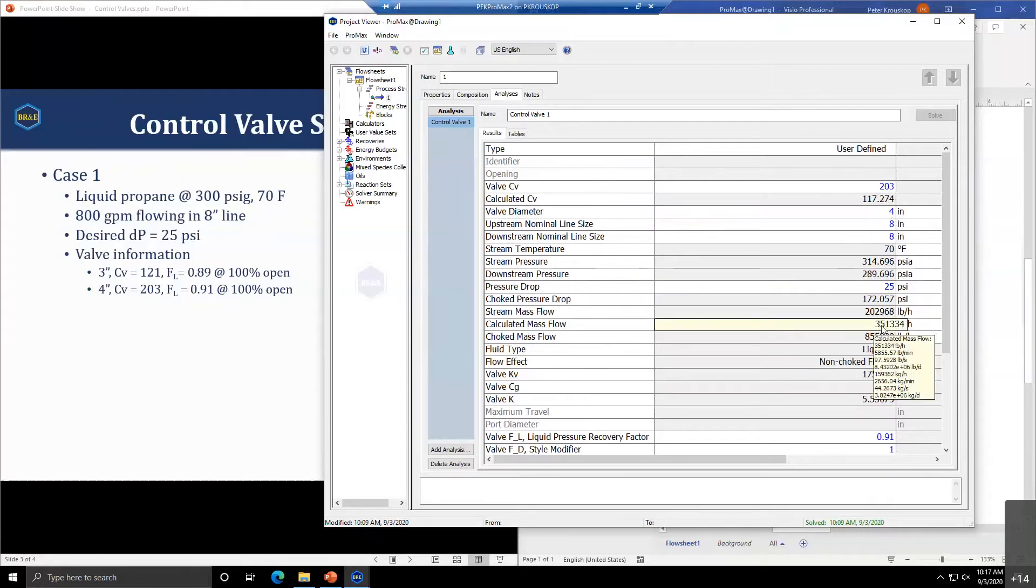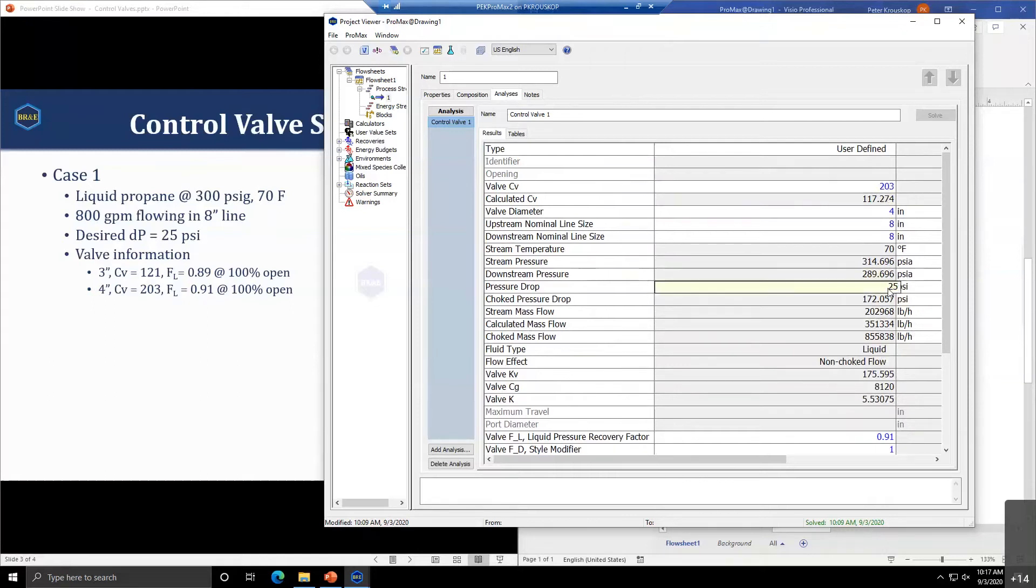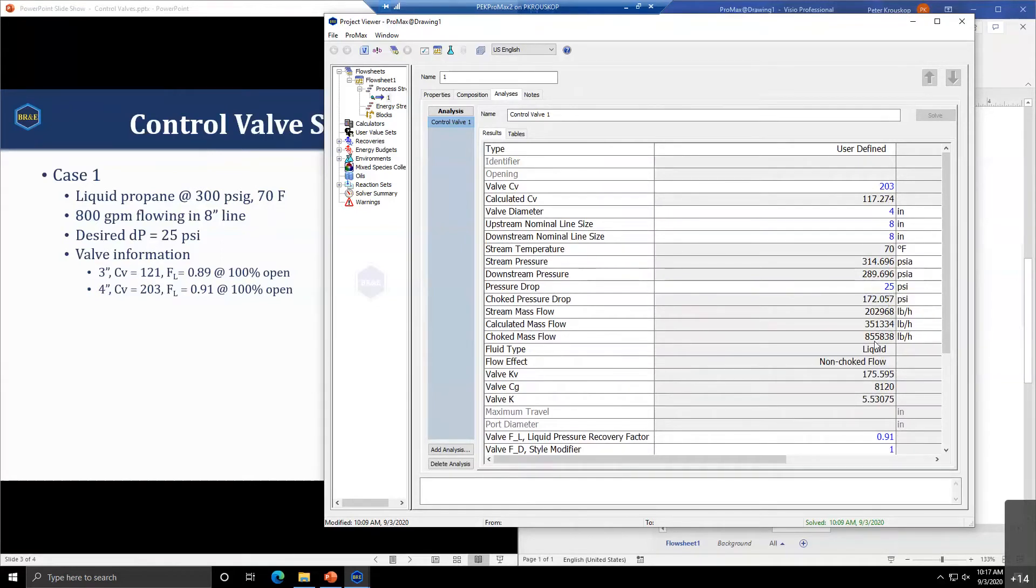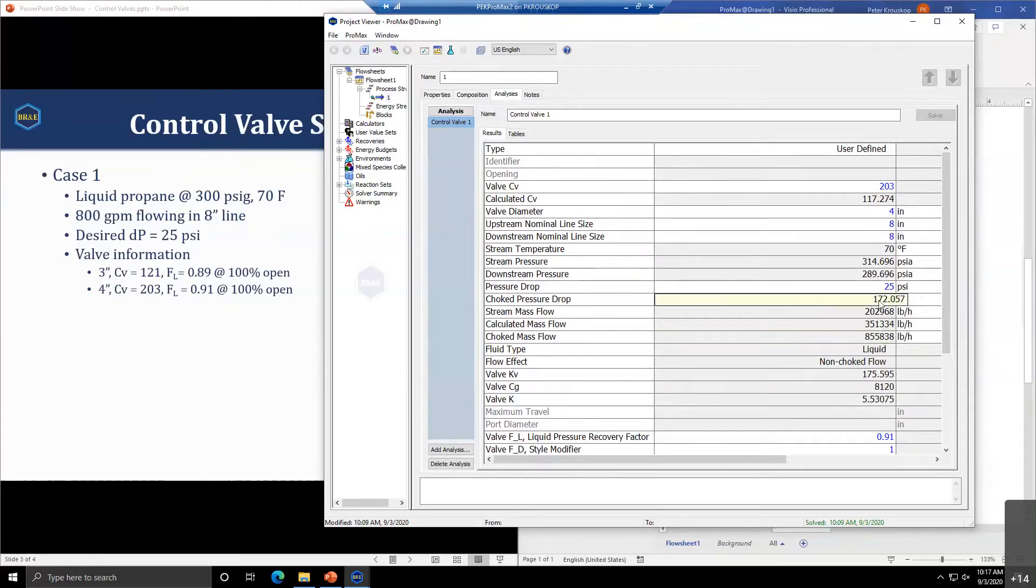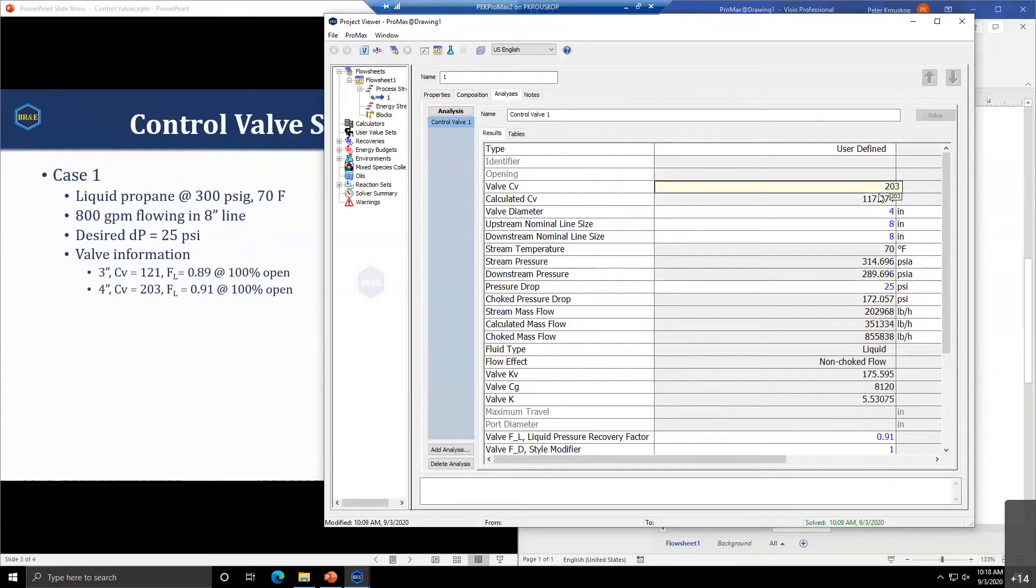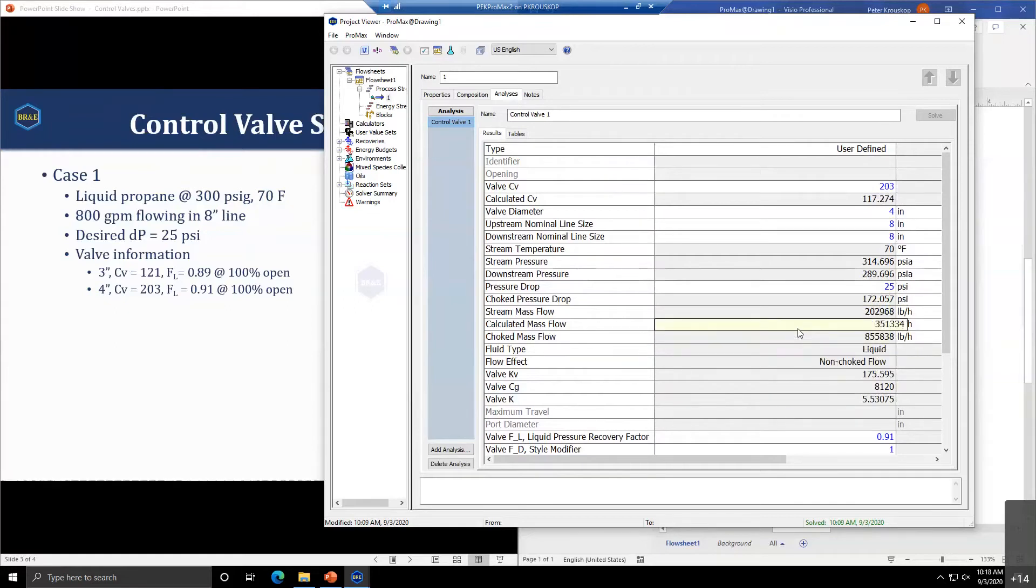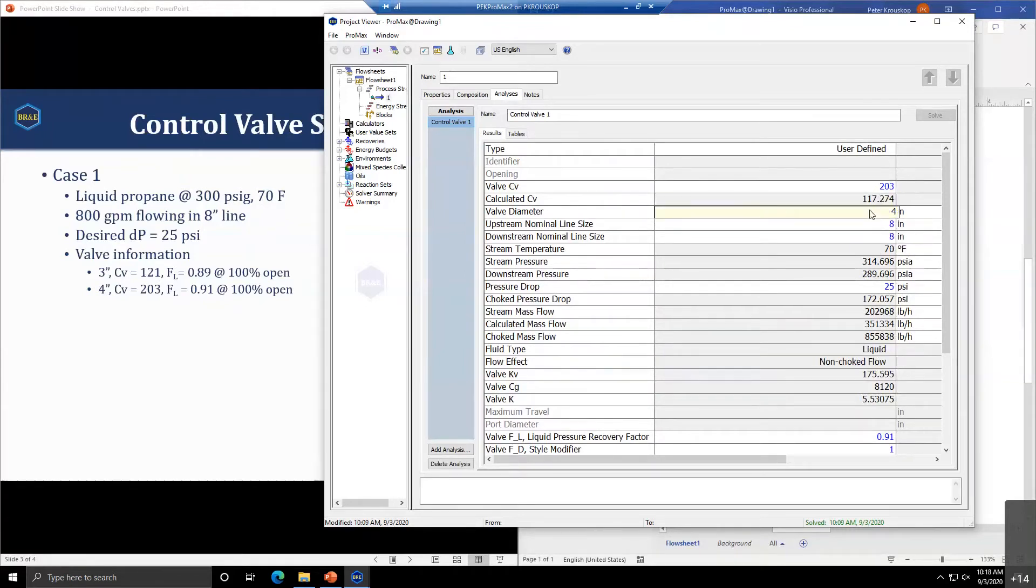The mass flow at 203 CV across a 25 pound pressure drop is 351,000 pounds per hour. This calculated mass flow is obtained by the CV you've put in and the pressure drop. The choked mass flow is the mass flow obtained when operating at the choked pressure drop.